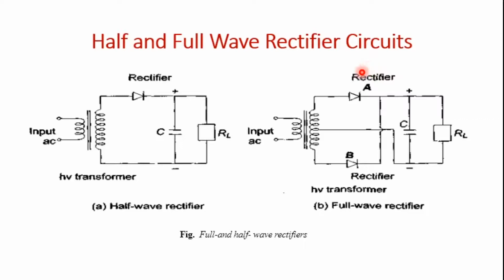The rectifier may be of electron tube or solid state devices. Nowadays, a single electron tube is available for peak inverse voltage up to 250 kV, and semiconductor or solid state diodes up to 20 kV. For higher voltages, several units are to be used in series. When a number of units are used in series, the transient voltage distribution along each unit becomes non-uniform, and special care has to be taken to make the distribution uniform.